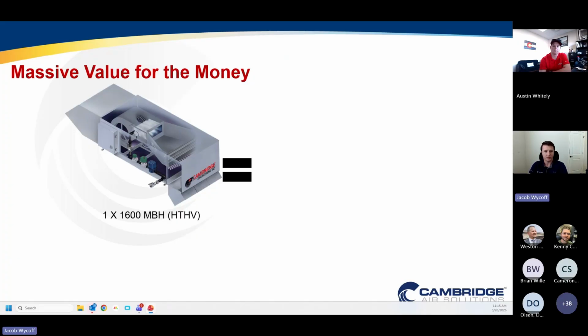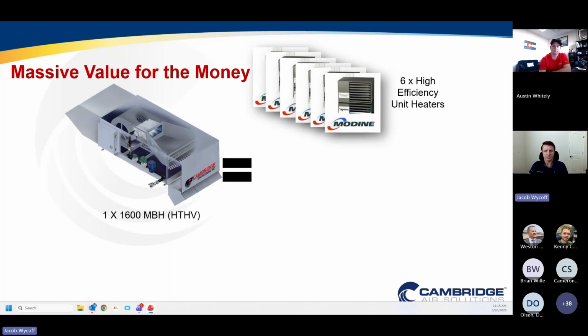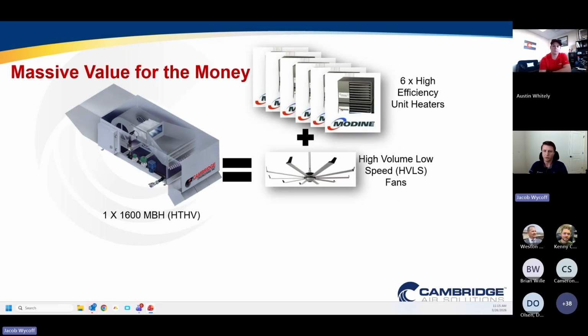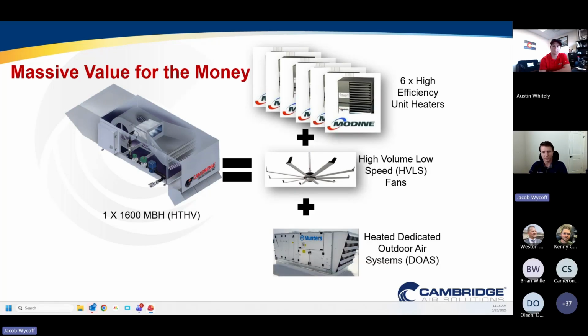Also a huge value for the money. So with a single S-series heater, you can displace 6 high-efficiency unit heaters. You no longer require an HVLS fan for air distribution and air movement and destratification. You also no longer require a heated dedicated outdoor air system to provide ventilation to the space. So as opposed to having 3 sets of equipment that all require installation, an integrated control strategy, service, and maintenance, you can replace that with a single HTHV unit that provides the heat the space needs in a single package, the ventilation the space needs in a single package, and the destratification that the space needs in a single package. Along with that, it's going to provide superior energy efficiency, and it's also going to last for an extremely long time, 25 to 30 years.